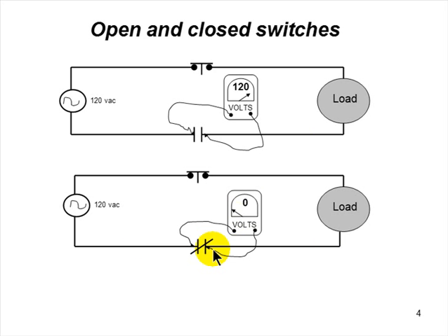In this case, I should read 0 because the voltage drop I'm reading is between the 2 points I'm reading. Back in this case, I read all the way from this side, back all the way around to the other side, and therefore I read this power. When I'm hooked up this way, there's continuity now because this is a closed switch, and I'm only reading the difference in voltage between this side of the contact and the other side of the contact. And that should be nothing.